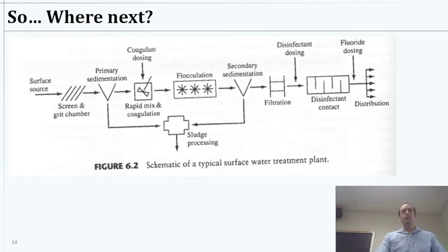For now, I'm just going to set that aside and say there's other types of sedimentation. What we just talked about would be called type 1, but there's type 2, type 3, type 4, whatever, to describe these different practical, in practice, what happens. Are you having what's called sweep, I don't know if it's sweep coagulation or sweep sedimentation. Anyway, sort of like all the particles start sticking together and sweeping through as if you're sweeping out the particles. So it becomes a little more relevant, those types of things, when we add coagulants and then let them flocculate, because then we have a condition where particles are really wanting to stick together.